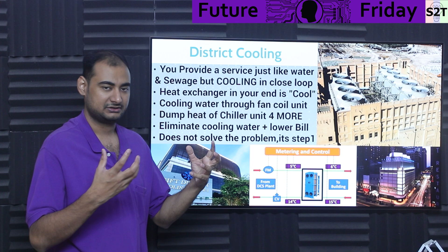That heat exchanger gives you a cold end. What do you do with it? For example, hotels generally don't have crazy high heat loads. In that scenario, you can literally run water through the building's load side and then run a fan coil unit. Many places do that. The fan coil unit dehumidifies and cools the structure, and the now-warm water comes back to the heat exchanger, leaches the heat, dumps it into the cooling loop, and things continue. That's one very cost effective, easy way of doing it, with very little energy cost.